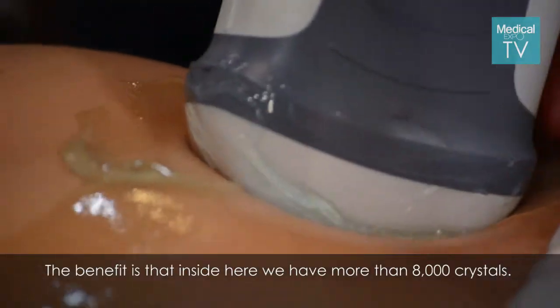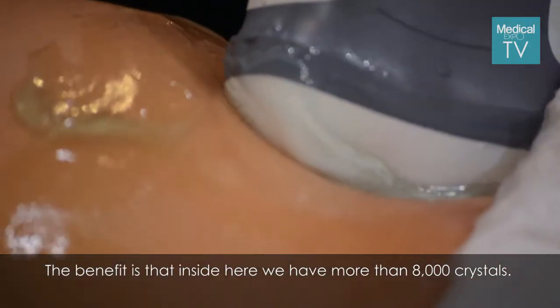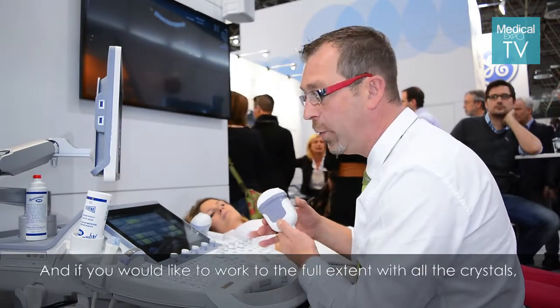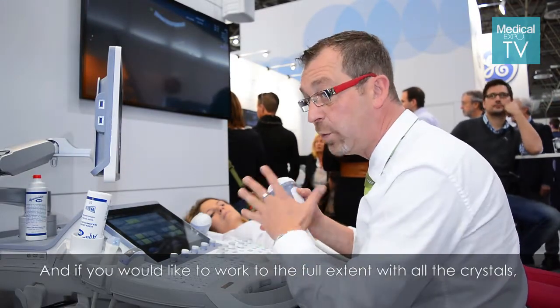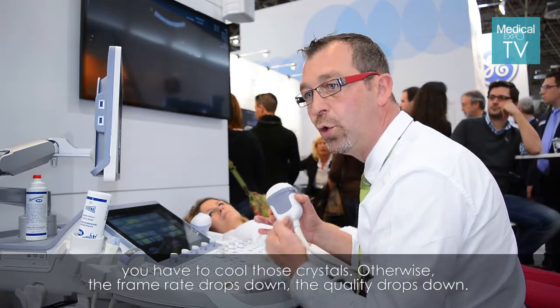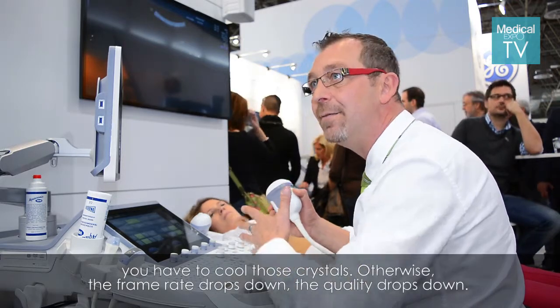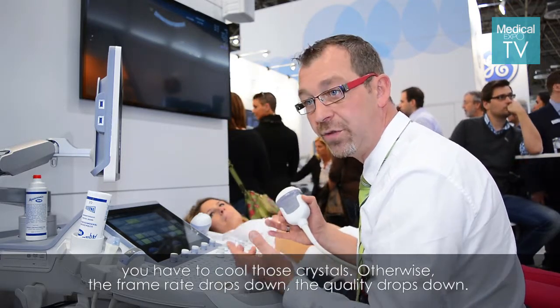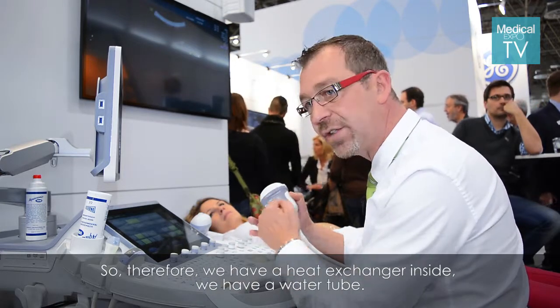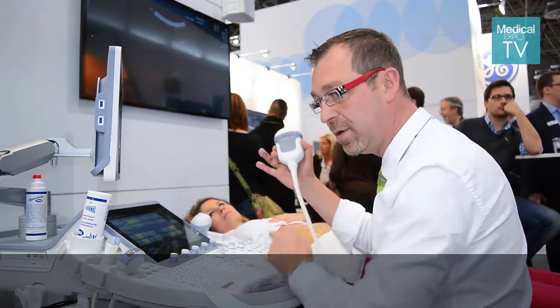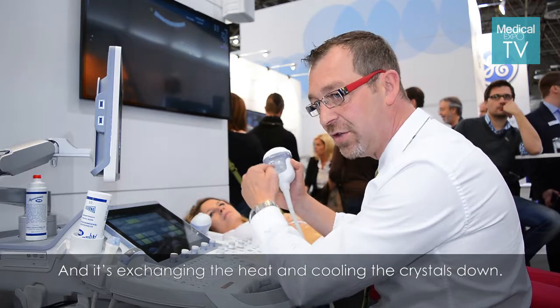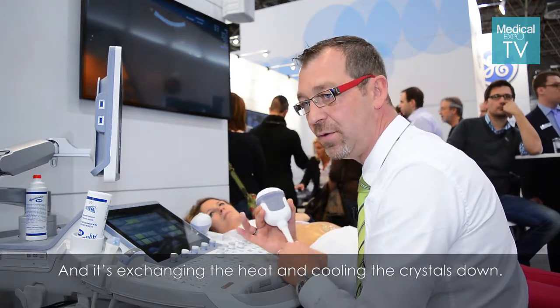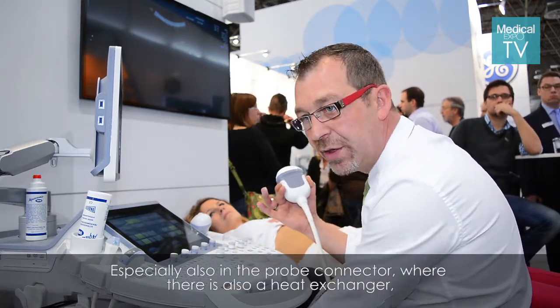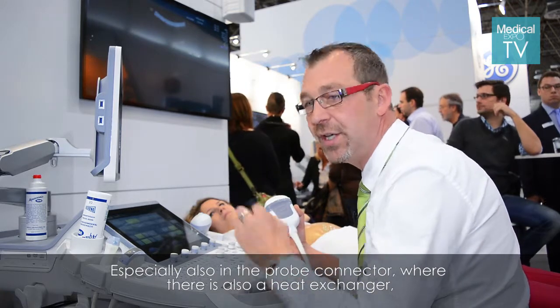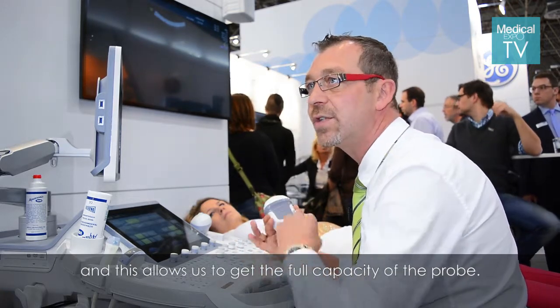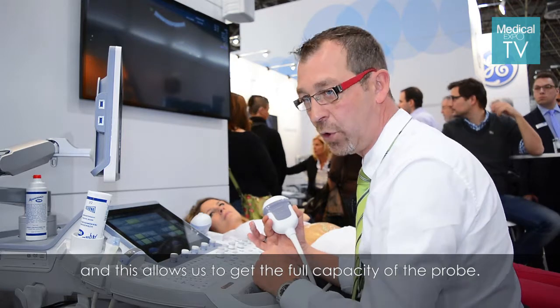The benefit is that inside here we have more than 8,000 crystals. And if you would like to work to the full extent with all the crystals, you have to cool those crystals. Otherwise, the frame rate drops and the quality drops. So therefore, we have a heat exchanger inside. We have a water tube, and it's exchanging the heat and cooling the crystals down, especially also in the probe connector, where there is also a heat exchanger. And this allows us to get the full capacity of the probe.